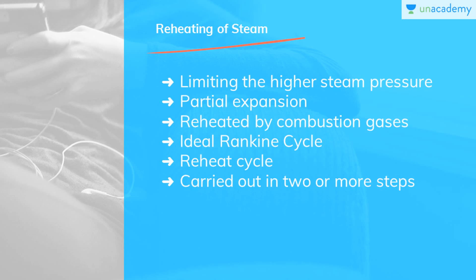Let's move on to reheating of steam. Reheating of steam is limiting the higher steam pressure in order to limit the quality to 0.88 of the turbine exhaust. All the steam after partial expansion in the turbine is brought back to the boiler, reheated by the combustion gases, and then fed back to the turbine for further expansion. In this reheat cycle, the expansion of steam from initial state 1 to the condenser pressure is carried out in 2 or more steps depending on the number of reheaters used.